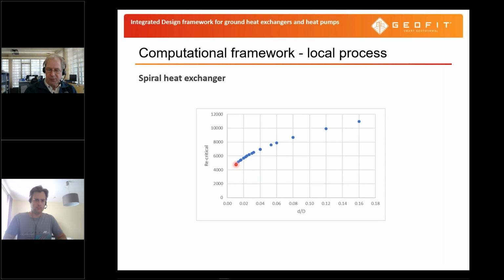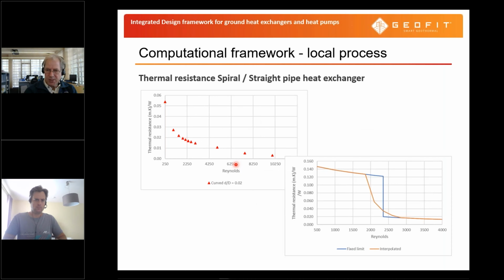Is this important? Is this a problem? Well, if we start looking at how this then translates into the thermal resistance, we can see that actually the thermal resistance, even for low Reynolds numbers, is relatively low. So in a spiral heat exchanger, due to the geometry, the thermal resistance is always quite low, even at low laminar flow Reynolds numbers.